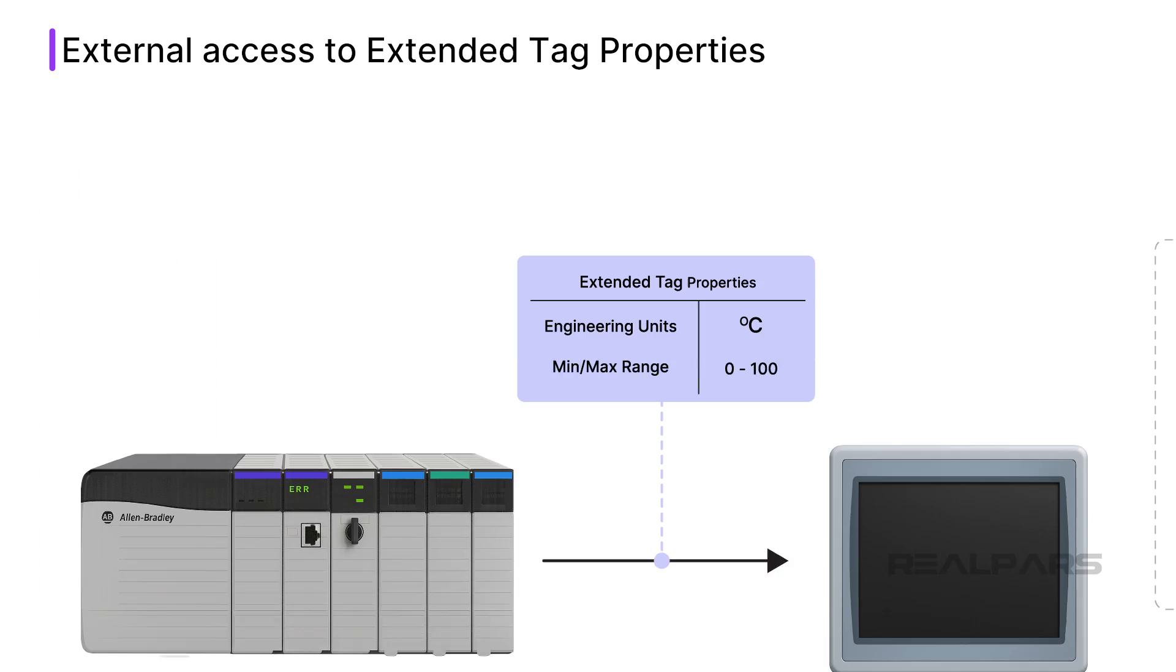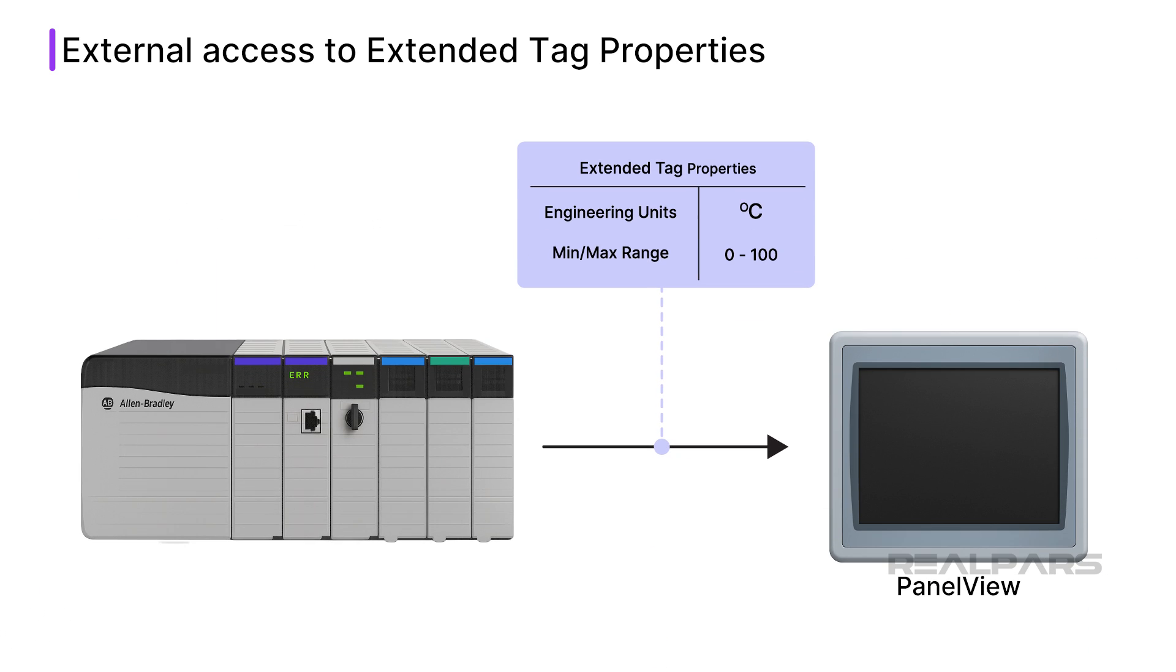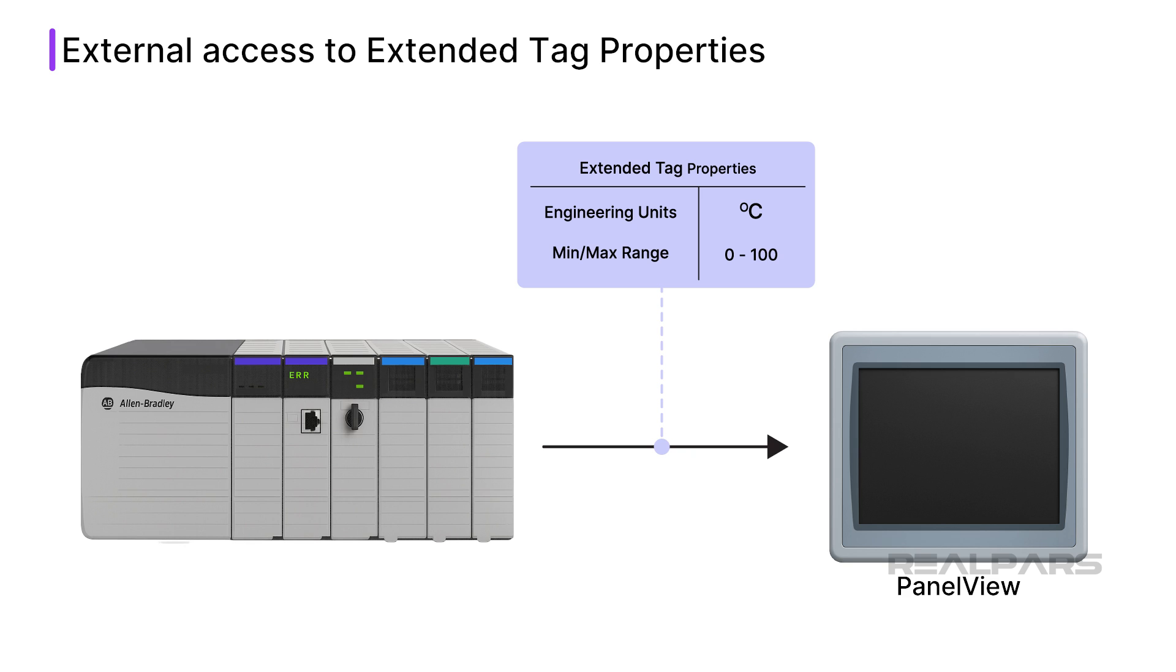Support for Extended Tag Properties allows an HMI application to pull contextual data from a tag, like the description of the tag or the engineering units that are associated with the value. Since the information is read directly from the PLC, there is less manual work required to parameterize HMI screens and faceplates.